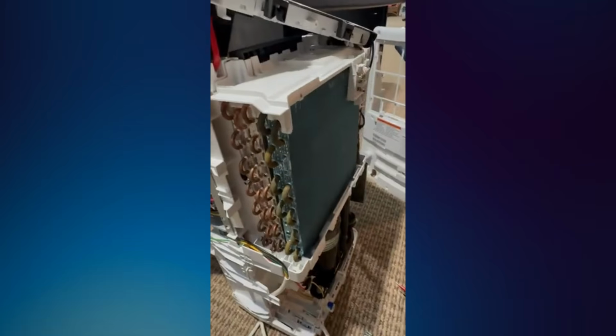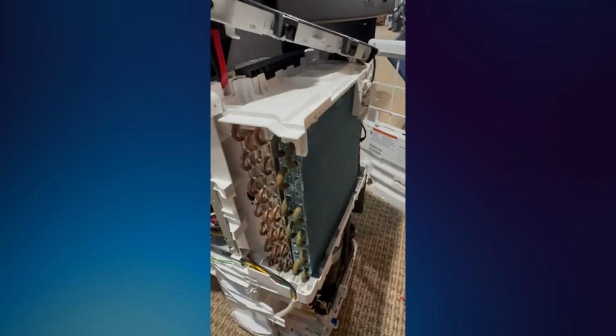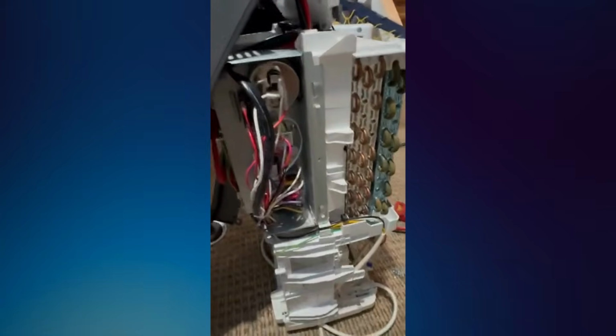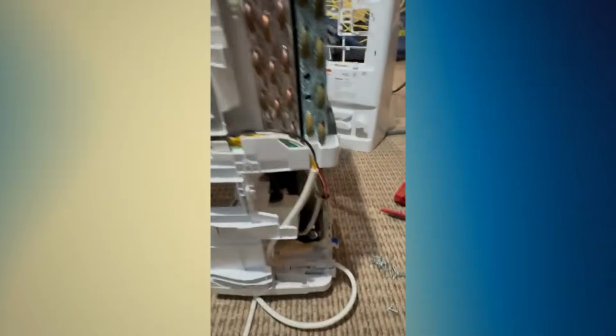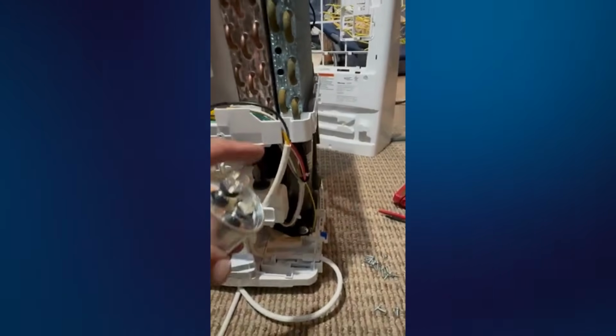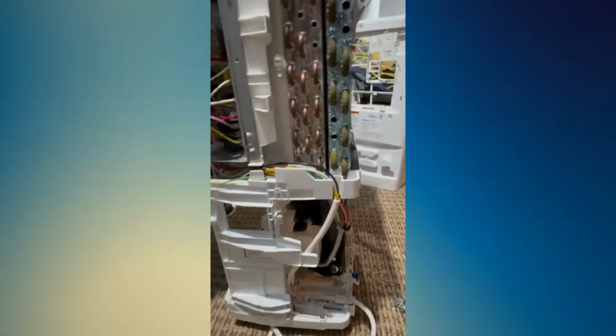These symptoms can point toward a weak capacitor, compressor overload, wiring fault, control board problem, or a failing compressor. If the compressor starts normally but E9 still appears, the humidity sensor, its connector, or the electronic board remains more likely.